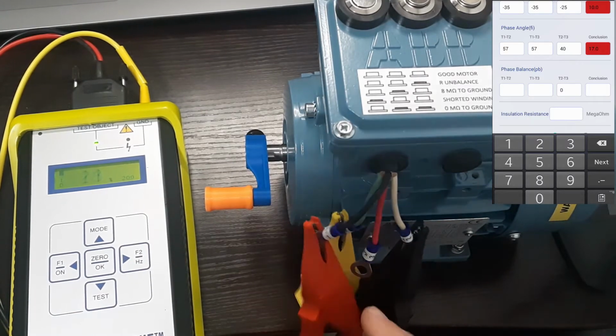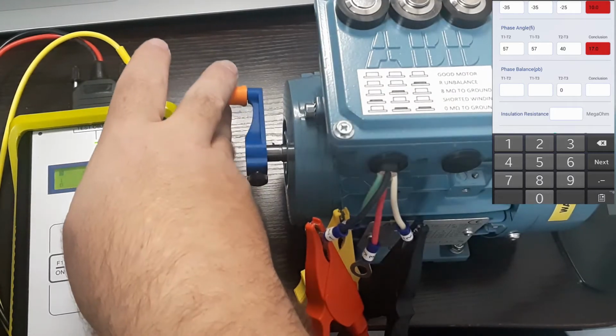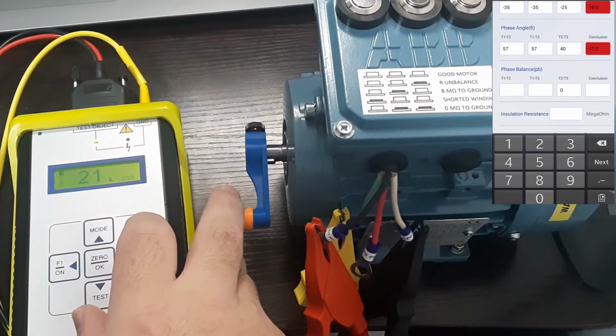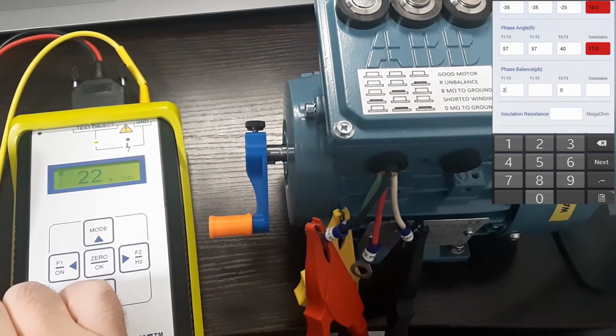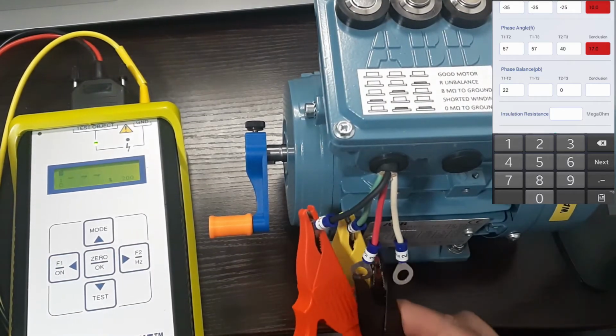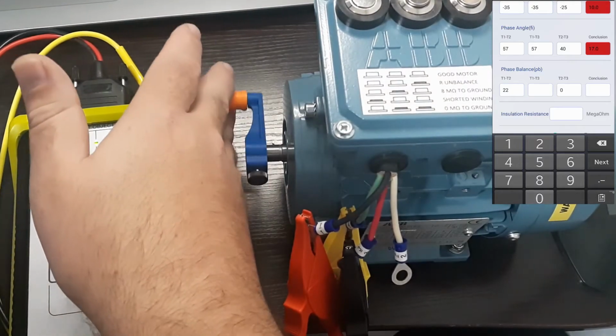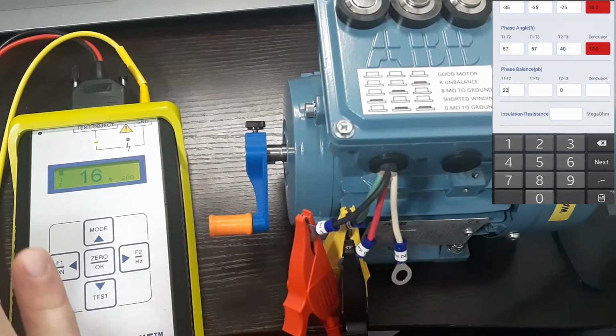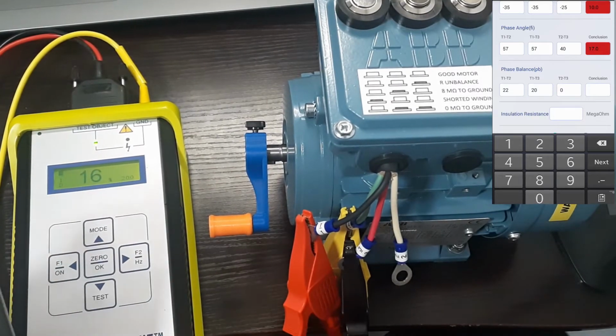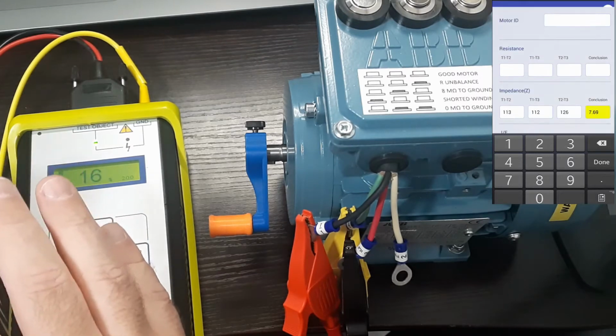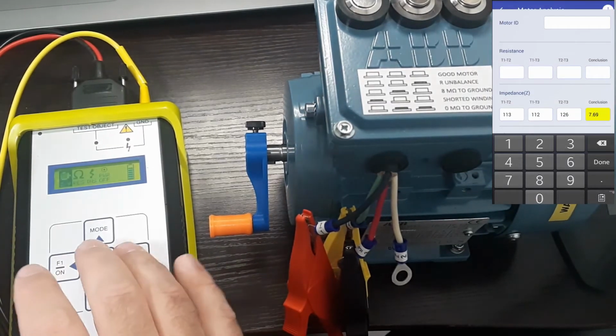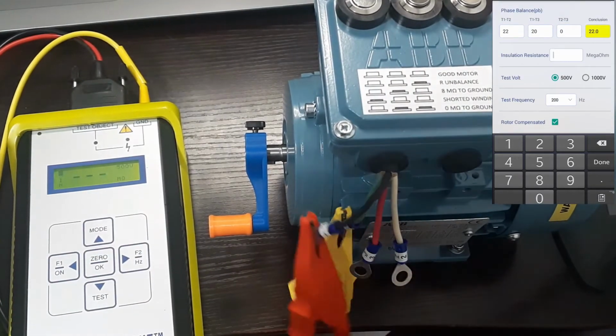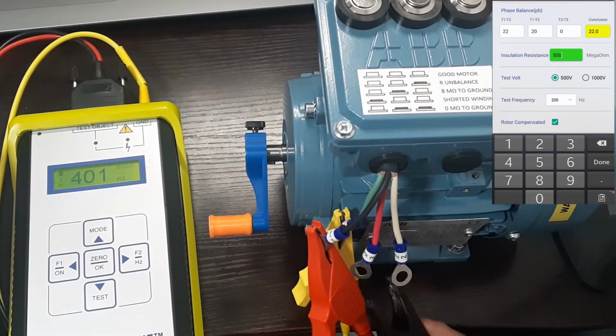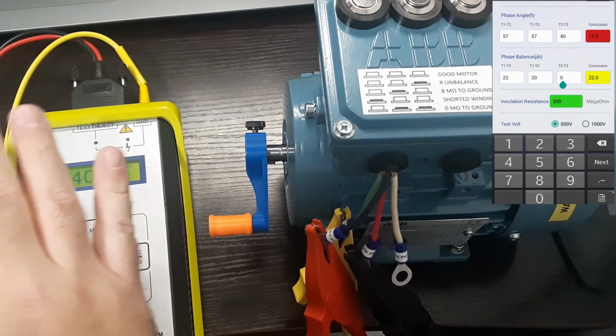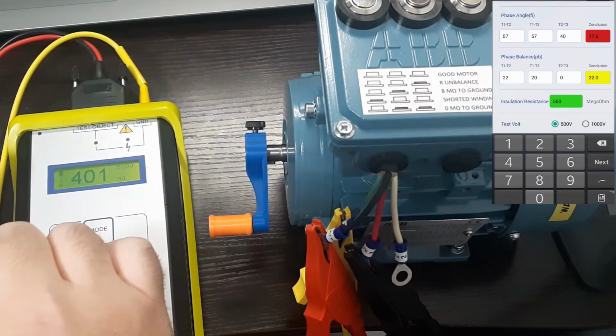So we'll go back to 1-2. We put our highest number down, so our highest number is 22. So we put that down in here. We'll go to 1-3. And we have 20. That's another number that doesn't look good. Well, not looking good so far. We'll head back to the main menu. We didn't do our insulation test, so we'll do that now. 500, so it does pass the insulation test. That's green. Test frequency was already set.